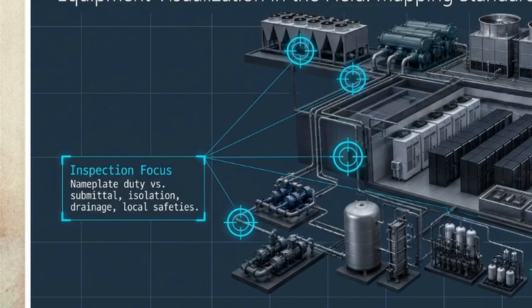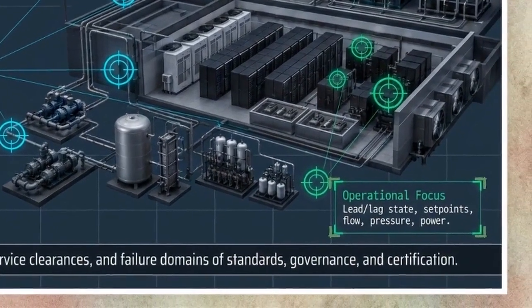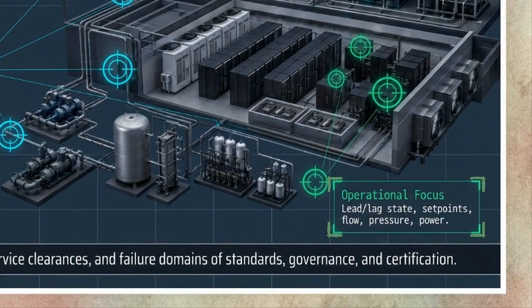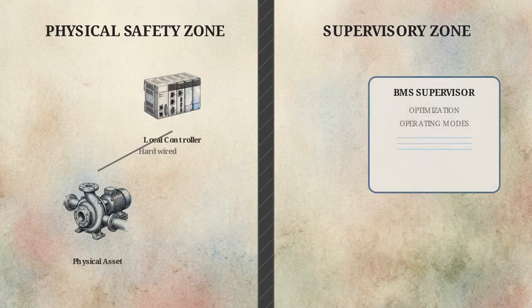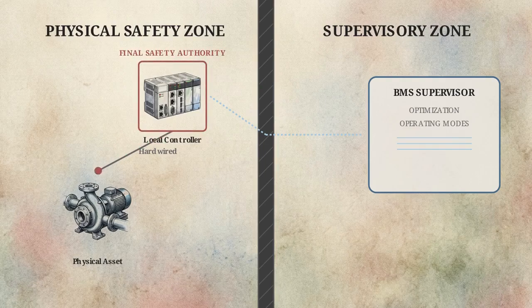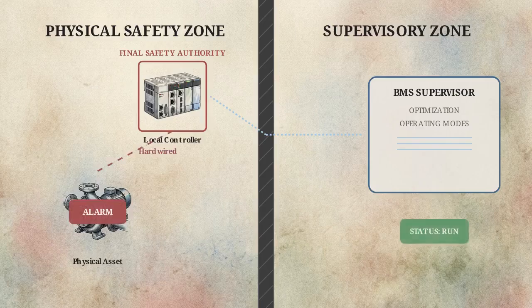The mechanical boundary defines specific supply and return conditions, establishing precise isolation points and pressure classes for every pipe and drain. The electrical interface dictates transitions between normal and standby power, enforcing the exact load shed sequence. The controls boundary relies on a rigid separation of duties. The building management system merely coordinates approved operating modes. The local hardware controllers retain absolute final safety authority over the physical asset.